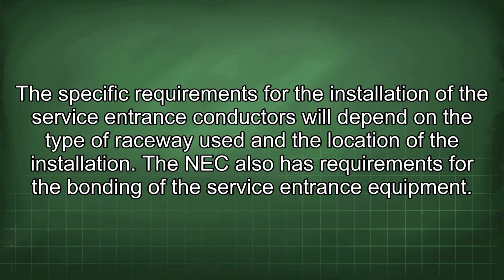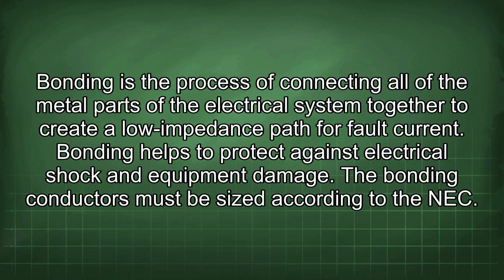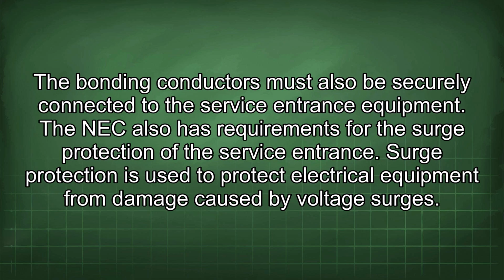The NEC also has requirements for the bonding of the service entrance equipment. Bonding is the process of connecting all of the metal parts of the electrical system together to create a low impedance path for fault current. Bonding helps to protect against electrical shock and equipment damage. The bonding conductors must be sized according to the NEC. The bonding conductors must also be securely connected to the service entrance equipment.